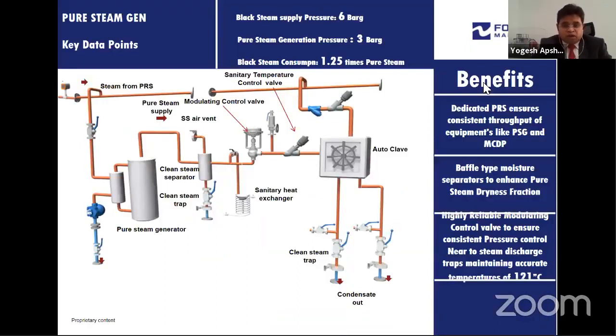So what we recommend in this gist, we can show you what our typical recommendations are. We recommend individual PRS for the pure steam generators. The steam is given to the pure steam generators, along with a condensate evacuation system. Once the pure steam is generated, it is distributed to process equipment, to a sanitary moisture separator or clean steam moisture separator, through clean steam traps.